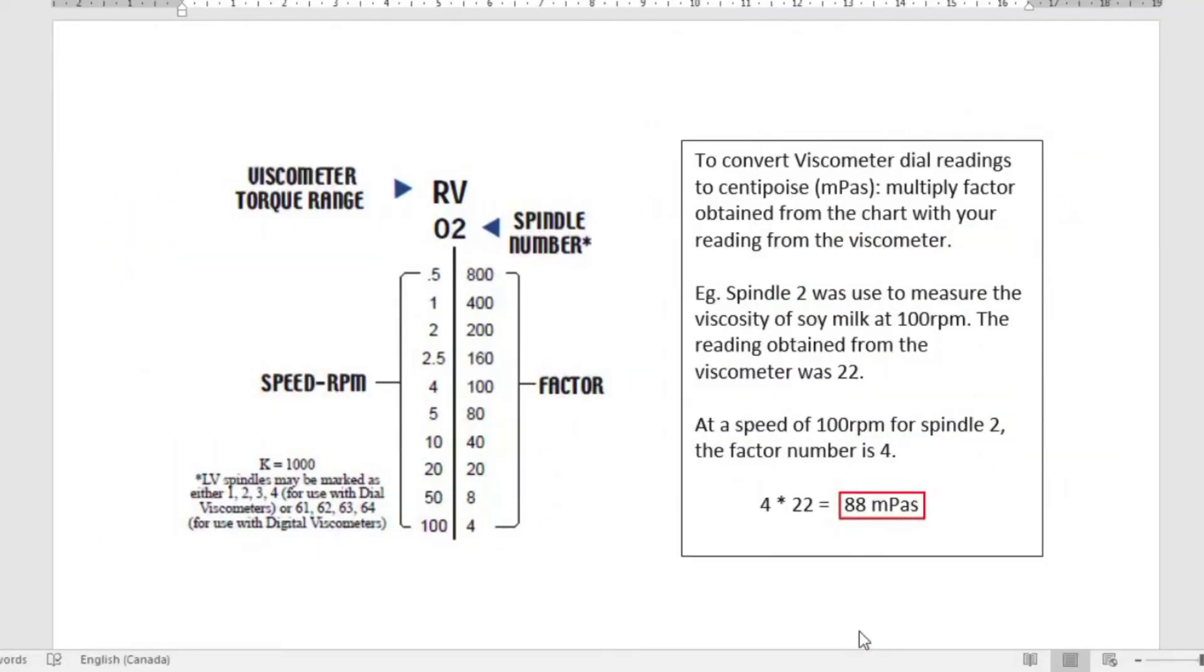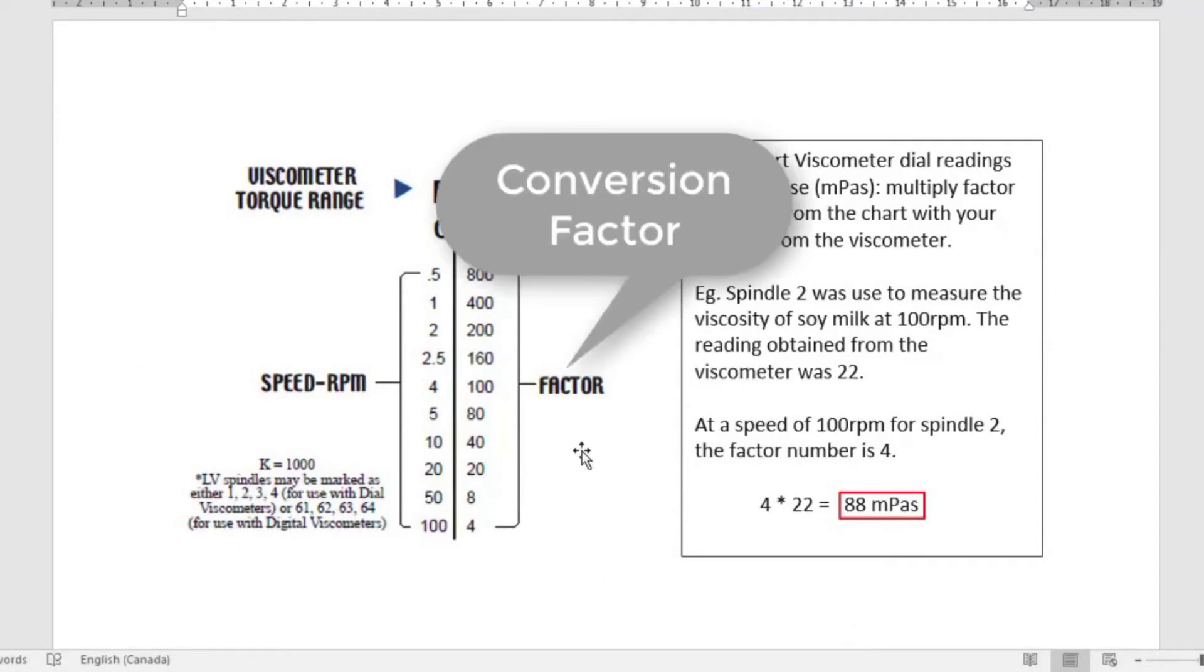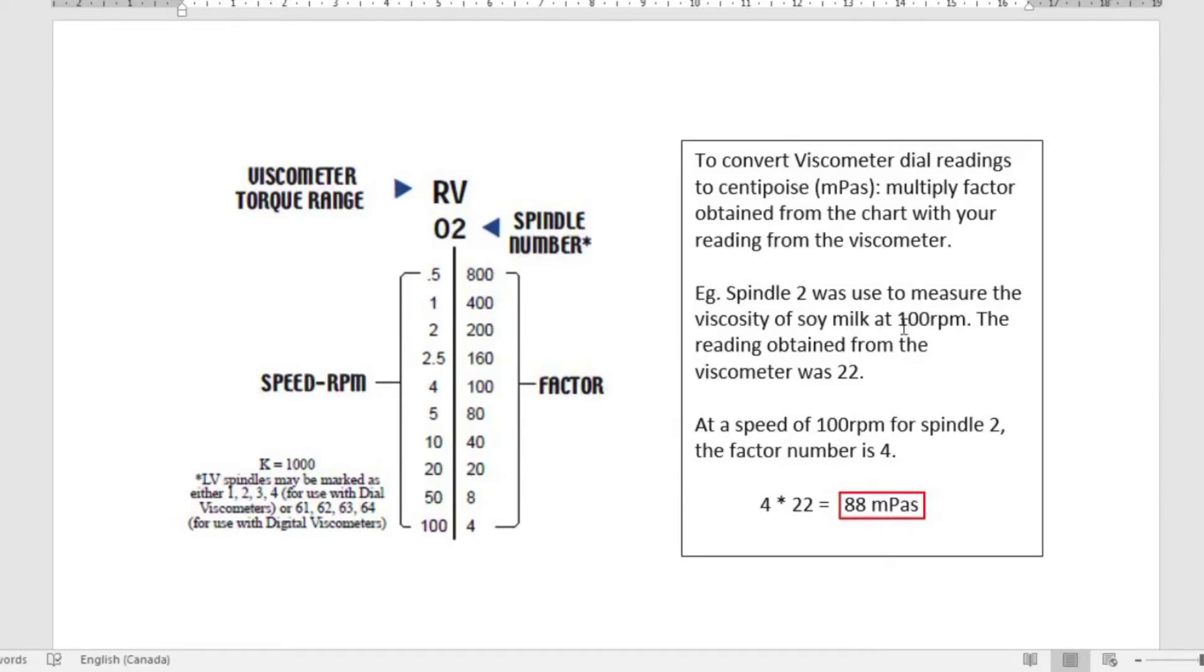Now that you have selected the correct conversion chart, the conversion factor can then be determined based on the speed of the viscometer during sample reading. In this example, a speed of 100 rpm was used, so its corresponding correction factor will be 4.